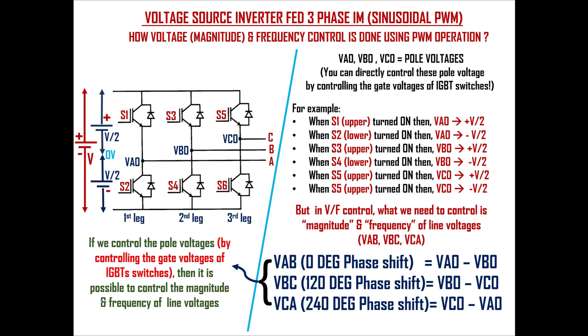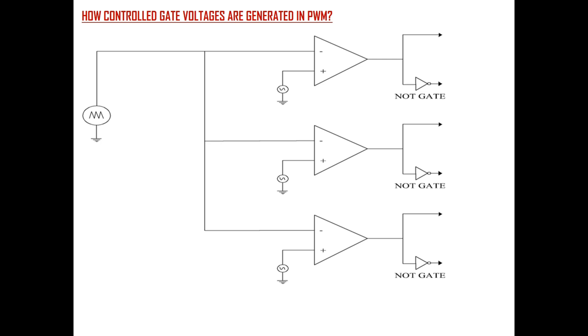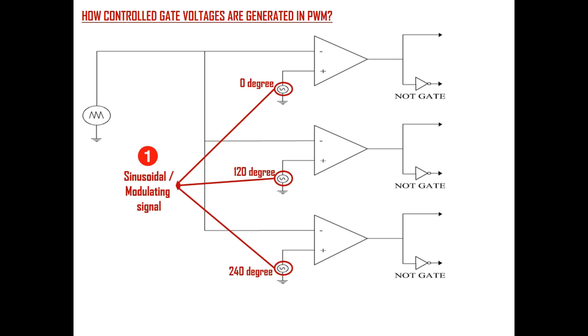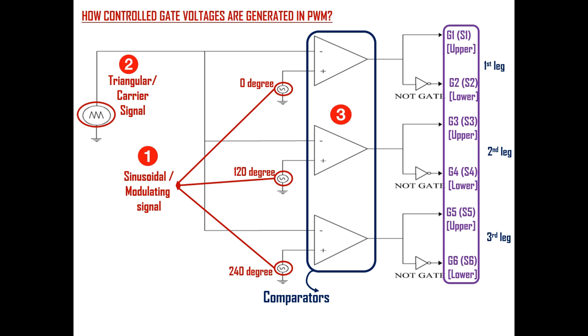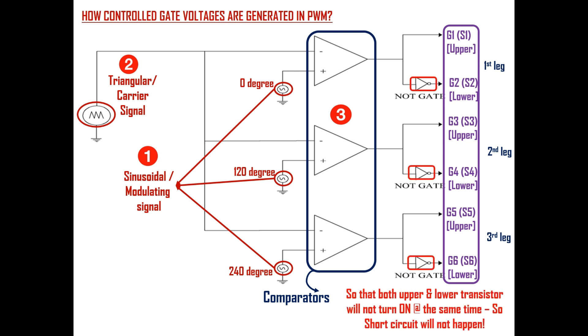The question is: how can controlled gate voltages be generated using PWM method? We can consider the generation of controlled gate voltage as a three-step process. First, create three sinusoidal signals called modulating signals with 120 degree phase shift. Second, create one triangular signal called the carrier signal. Third, each sinusoidal signal and the triangular signal are compared using three comparators, whose outputs generate the gate voltages for the upper and lower switches of each leg. Gate voltages to the lower switches S2, S4, and S6 are given through a NOT gate, so both transistors in the same leg will not turn on simultaneously, avoiding a short circuit.